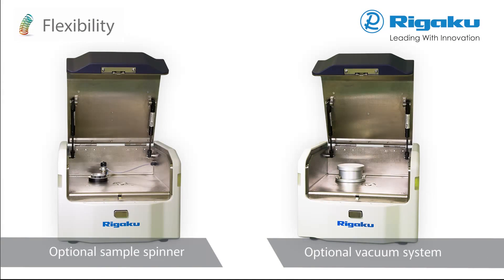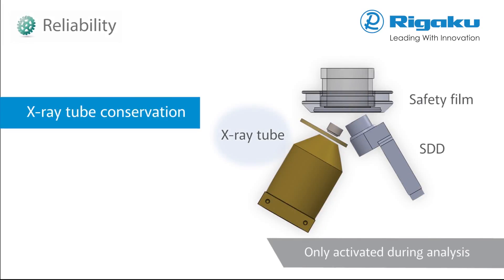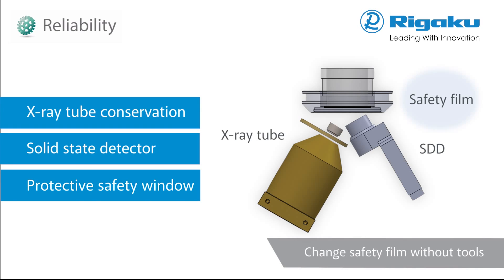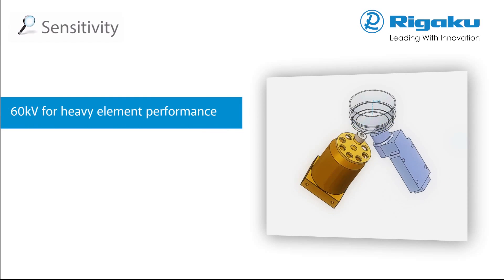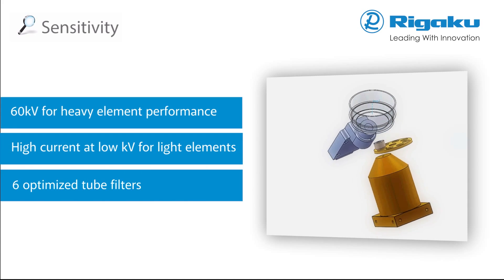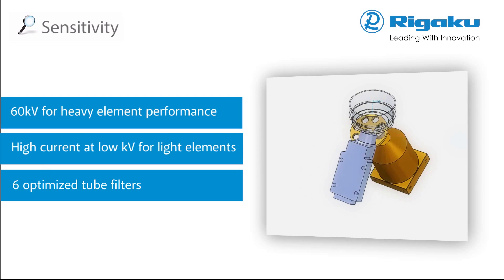Rigaku XRF spectrometers are the most reliable in the world. The NEX DE was engineered for X-ray tube conservation and employs solid-state detector technology. Optics are protected by safety film that requires no tools to change. Sensitivity is primarily a function of the X-ray tube and detector. 60 kilovolt excitation and six optimized filters, and high current at low voltage, delivers highest sensitivity across the periodic table.